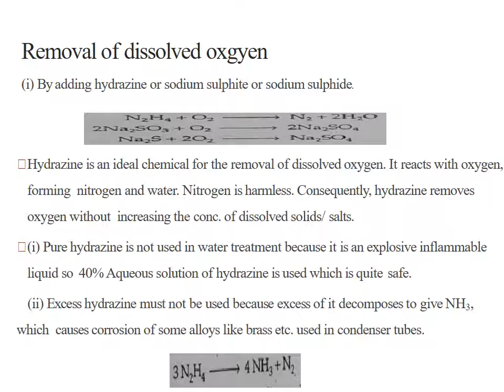Pure hydrazine is not used in water treatment because it is an explosive, inflammable liquid. So a 40% aqueous solution of hydrazine is used, which is quite safe. Excess hydrazine must not be used because excess of it decomposes to give NH3, which causes corrosion of some alloys like brass used in condenser tubes. So avoid using excess hydrazine, because it is converted to ammonia, and the ammonia gas produced inside the boiler can cause corrosion of some alloys used in various parts of the boiler machinery system.